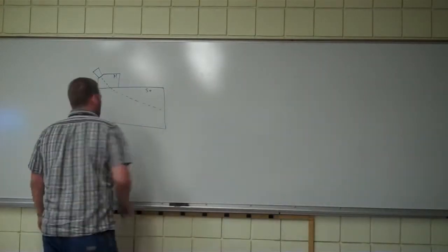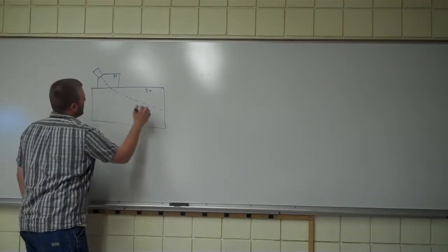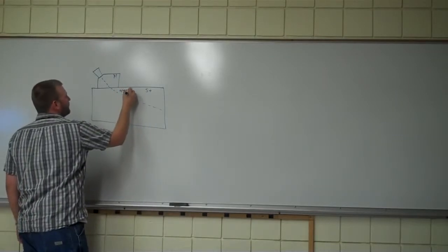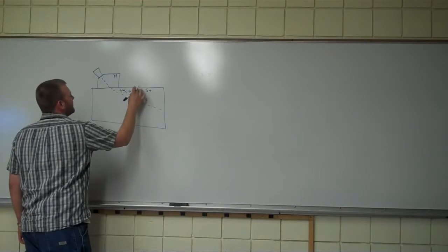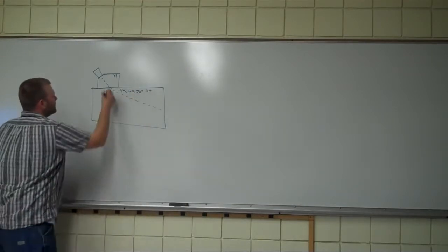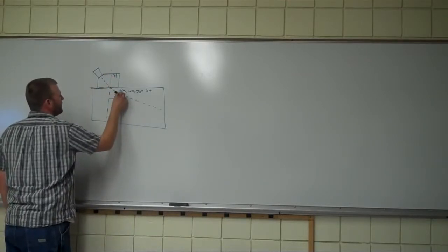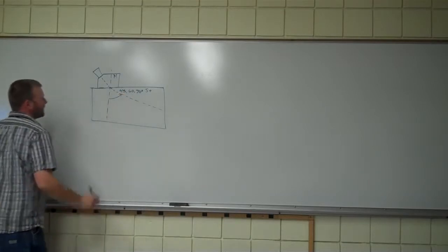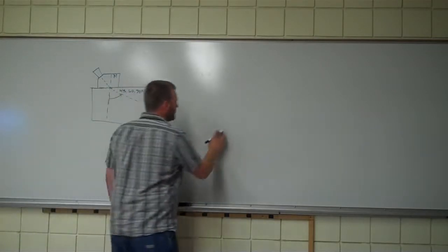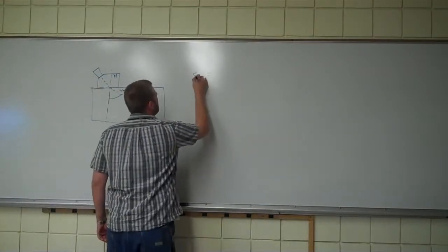So, here's our picture, here's our chunk of steel, never mind the fact that it's not level. We've got a shear wave coming out here. Let's just for fun say that it's going to be either 45, 60, or 70 degrees, and that's measured in a plane like this. So we need to know the calculation that actually makes that happen. That would be this one.